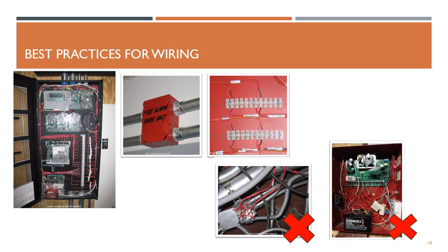Labels can also be used to achieve this same objective. In the picture below, we see a box that is difficult to identify if we are standing below it, because the box is uncovered, and also you see a total mess of cables, which for future preventive and corrective maintenance actions, will be a big issue.